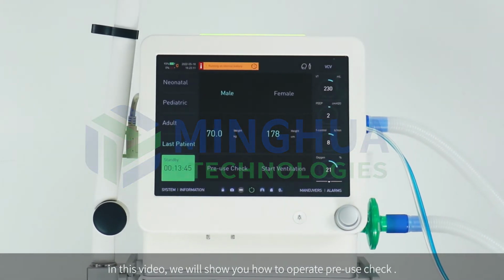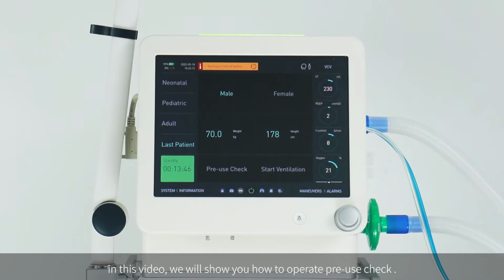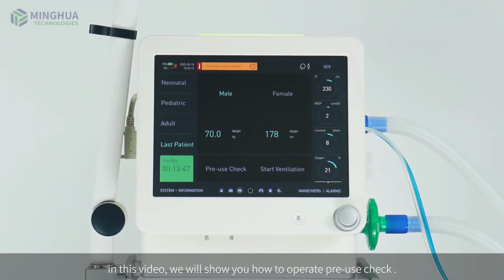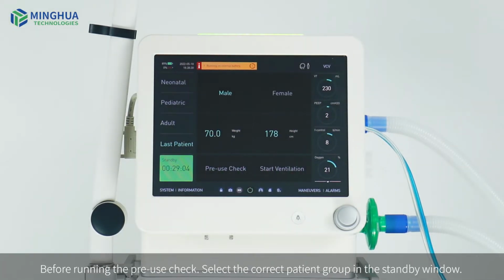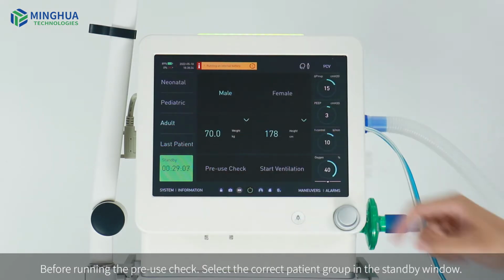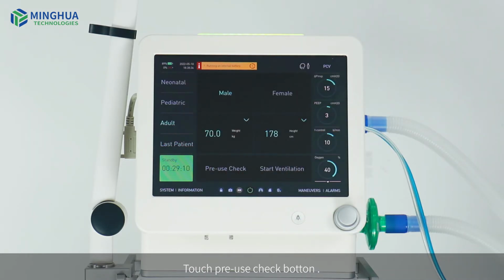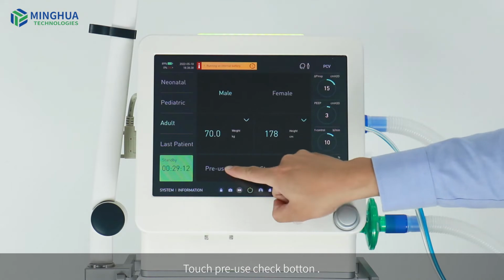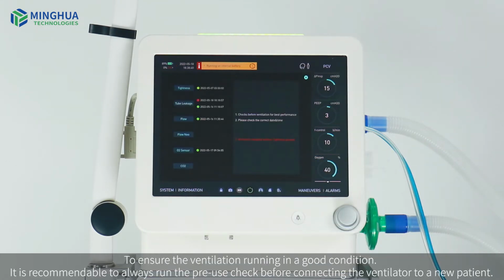In this video, we will show you how to operate pre-use check. Before running the pre-use check, select the correct patient group in the standby window. Touch pre-use check button. To ensure the ventilation running in a good condition, it is recommendable to always run the pre-use check before connecting the ventilator to a new patient.